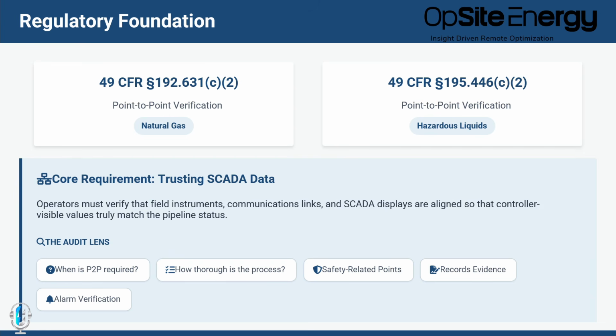What are your safety-related points? Yeah, so what I'm hearing from you is that you're really wanting to verify field instruments, communication links, and your display. So it's sort of like a triangle of information: looking at that field instrument, the communication link is working, and that your SCADA displays are aligned with the actual values being represented from the field device.